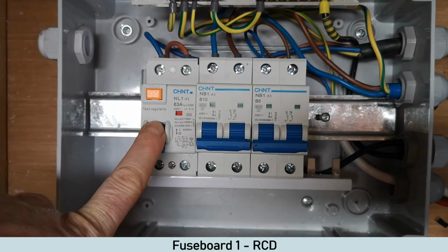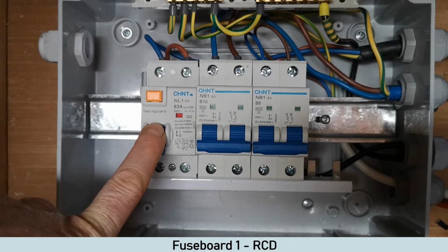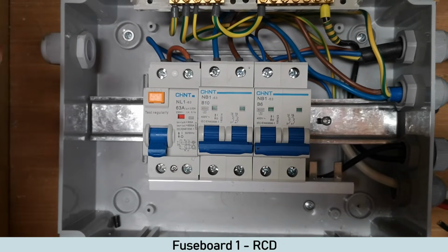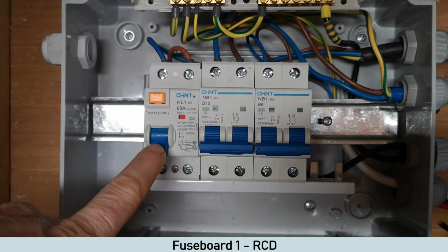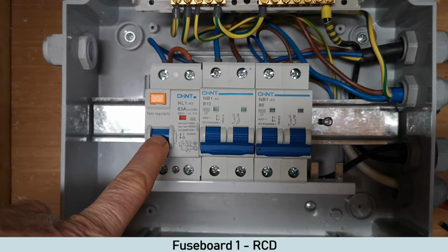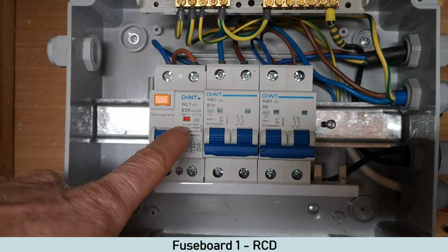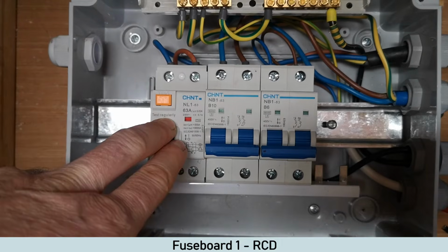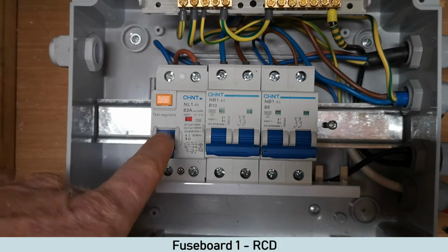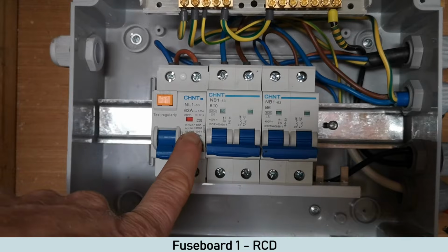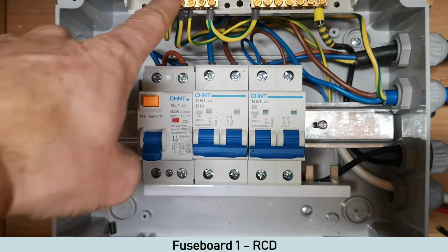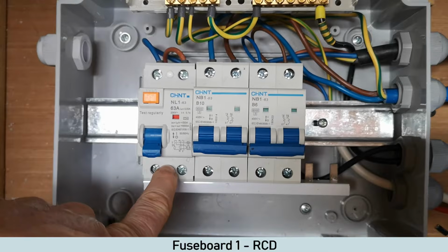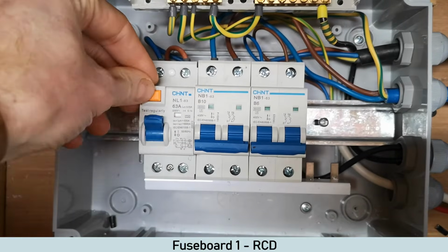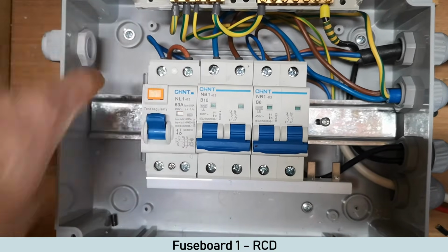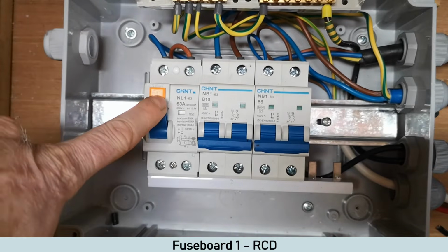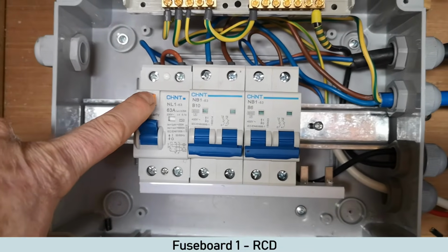What will happen if you have a type AC and plug in appliances that have DC components, it could actually affect the way that this RCD works. Type A's are a bit harder to find and a bit more expensive than AC, but you can find them, and I will put a link to this exact one in the description below. So obviously mains comes into the top, goes through the RCD, and then I think, yeah, I've got power on at the moment. So there is a test button on an RCD, and that means there's power coming in. So I've got the hookup connected.